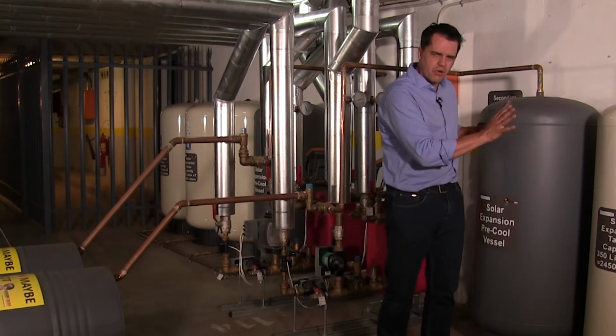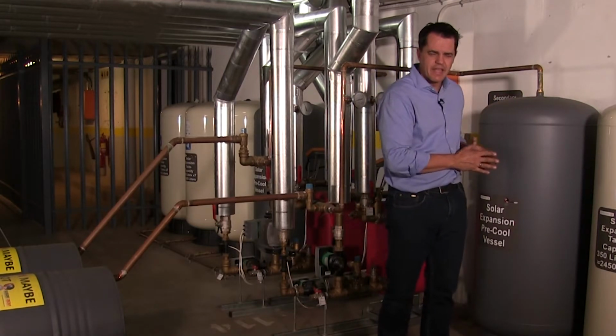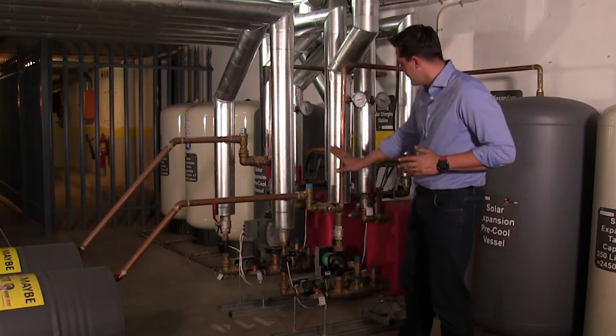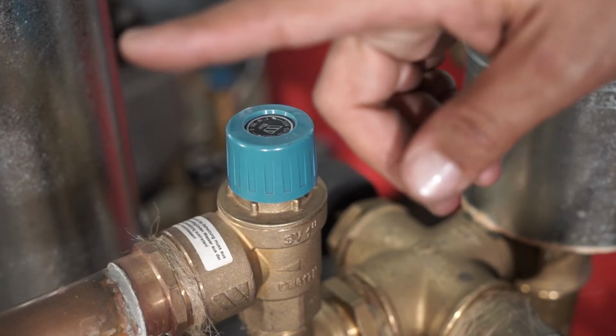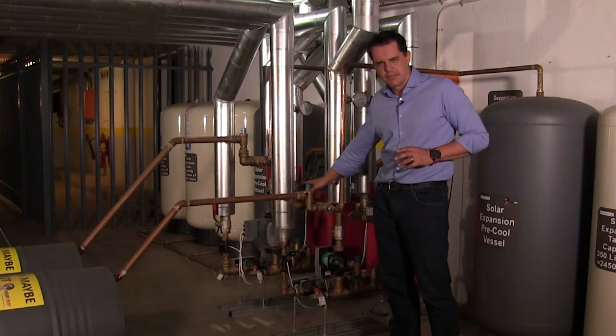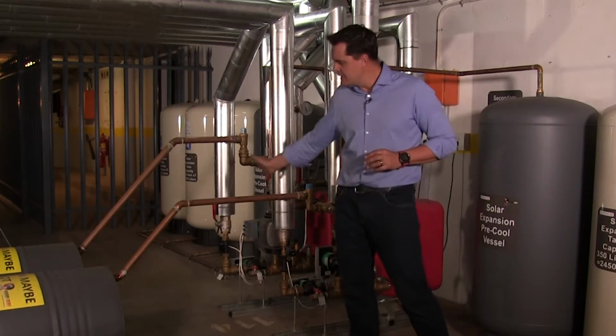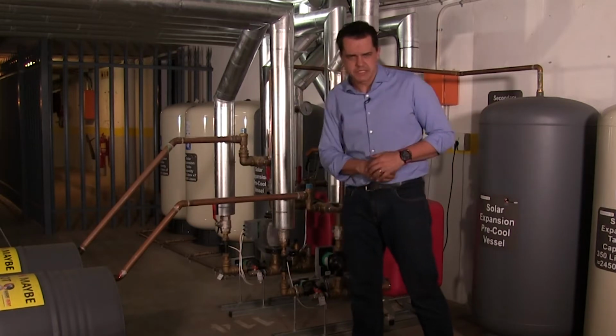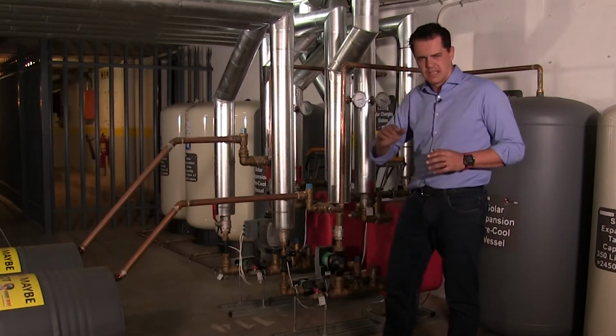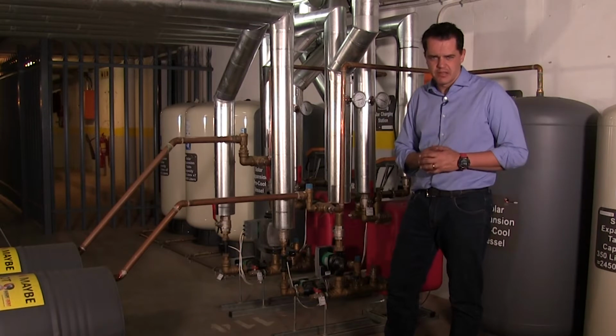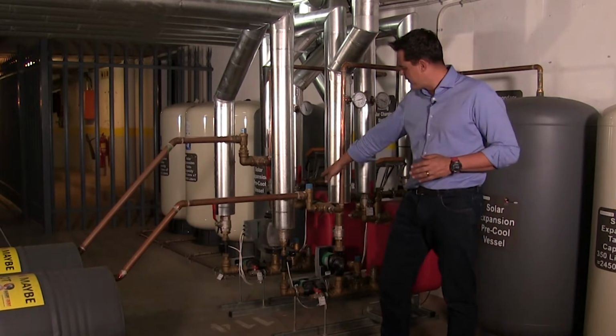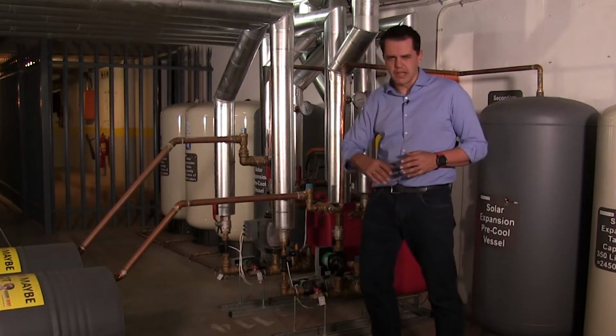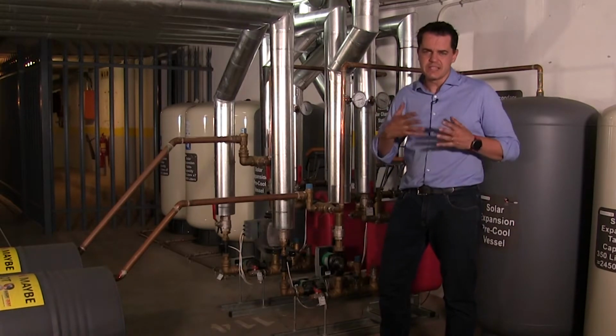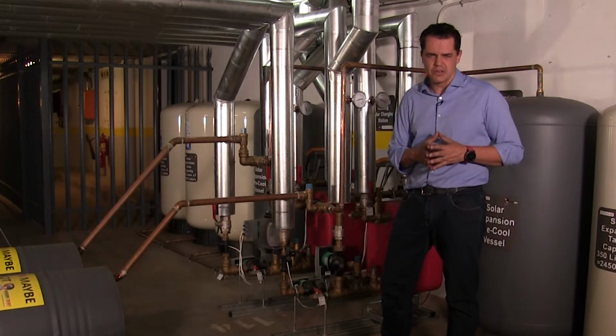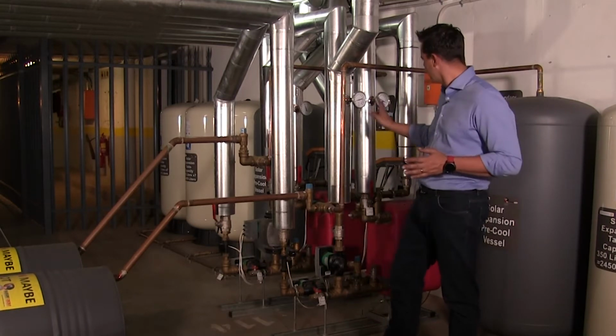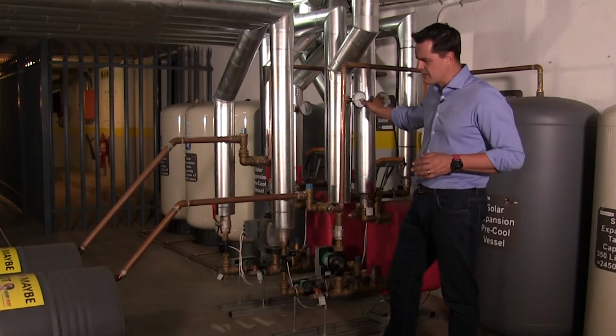If anything goes wrong with this expansion protection, there's a backup safety, and that's the safety overpressure valve. If this opens up, it will release the glycol into these drums to in fact protect the system as a safety failure. When that glycol is released, it means that the system doesn't have the hydraulic capacity to in fact circulate. Then there will be no temperature differential here.